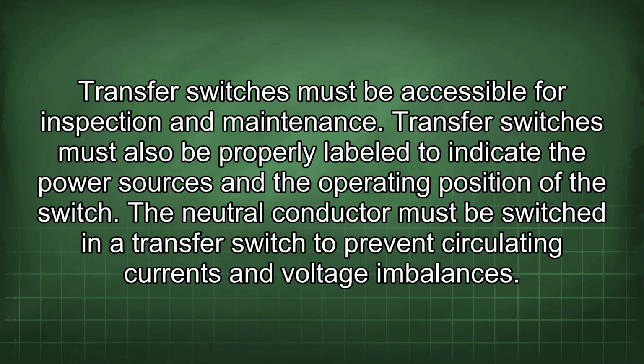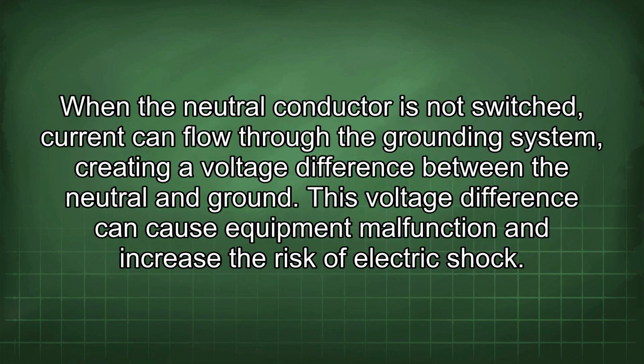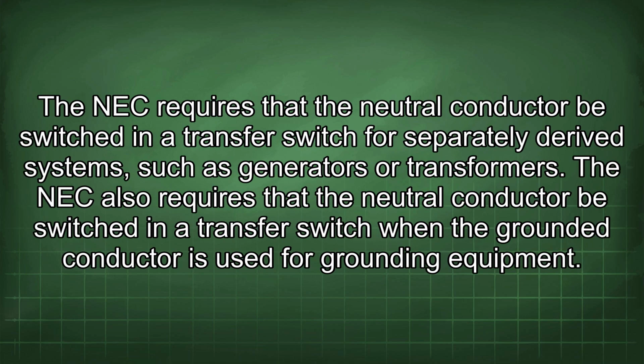The neutral conductor must be switched in a transfer switch to prevent circulating currents and voltage imbalances. When the neutral conductor is not switched, current can flow through the grounding system, creating a voltage difference between the neutral and ground. This voltage difference can cause equipment malfunction and increase the risk of electric shock. The NEC requires that the neutral conductor be switched in a transfer switch for separately derived systems such as generators or transformers. The NEC also requires that the neutral conductor be switched in a transfer switch when the grounded conductor is used for grounding equipment.